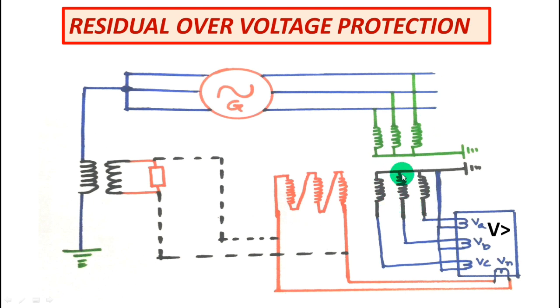If this connection is made, you have to be careful that this PT should be either 3 single phase PT unit or a 5 limb PT. Because only using this PT, these two PTs, the 0 sequence flux will be residual flux will be flowed. Otherwise if you use a 3 limb PT, there the residual flux will not be available.